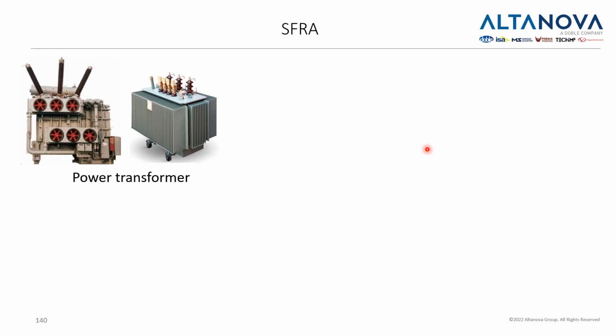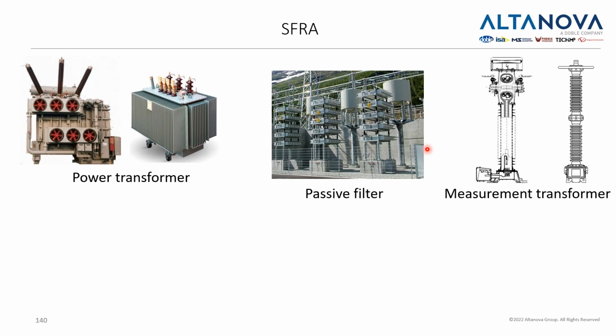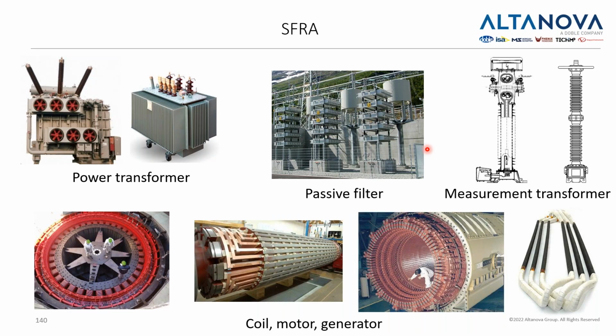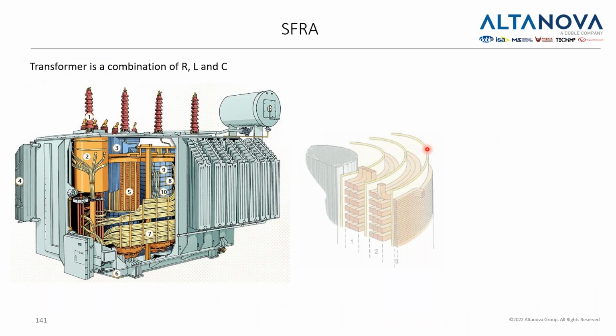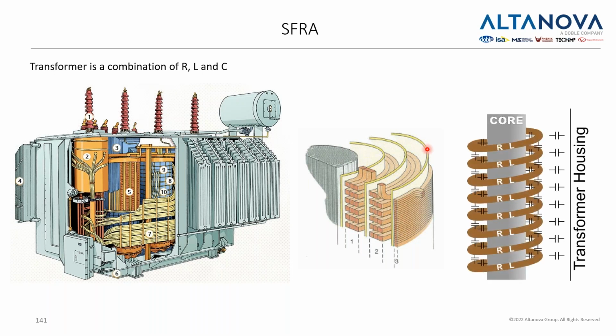Now, sweep frequency response analysis is the next test we're going to cover. This test can be done on many assets: power transformers, filters, measurement transformers, and rotary machines. The idea of this is that the transformer is a complex system of resistances, inductances, and capacitances. Now, if we were to generate a small voltage, not a big one, on the primary and measure on the secondary and then do vice versa, we would get a transfer function. So let me show you.